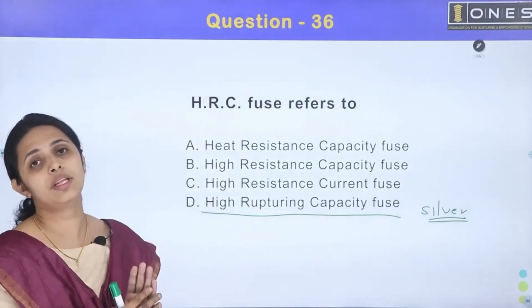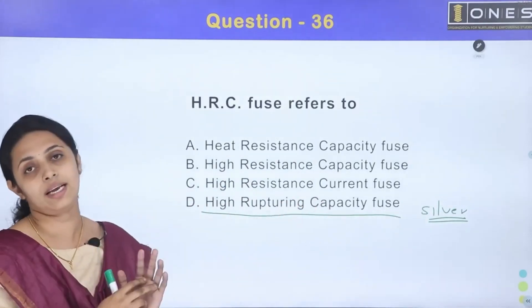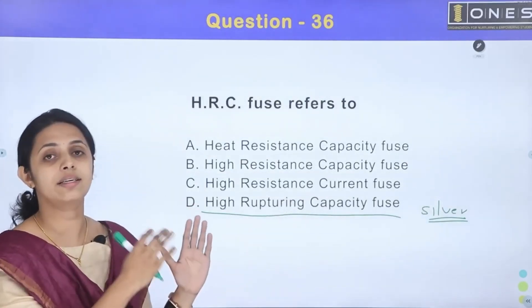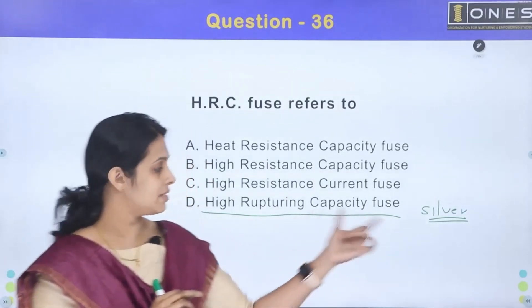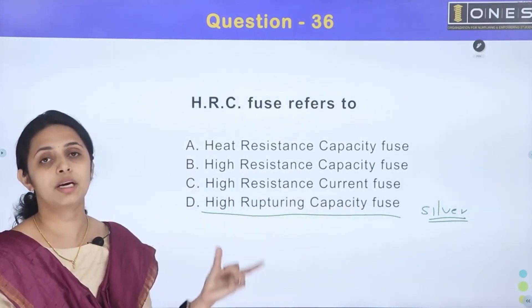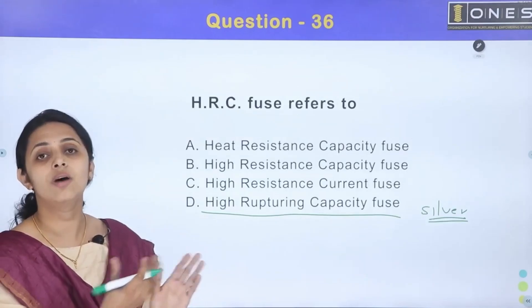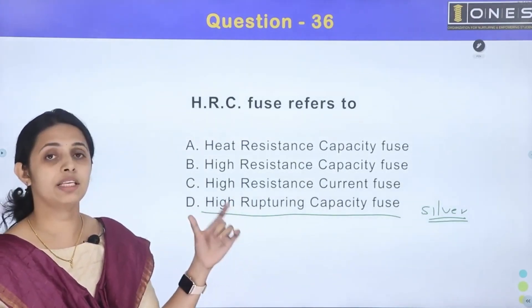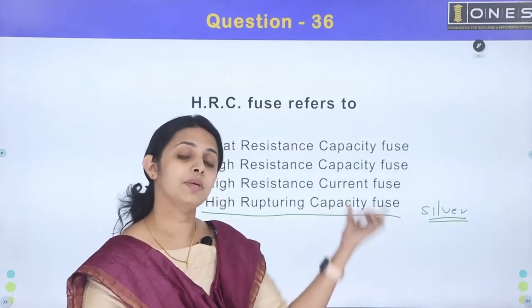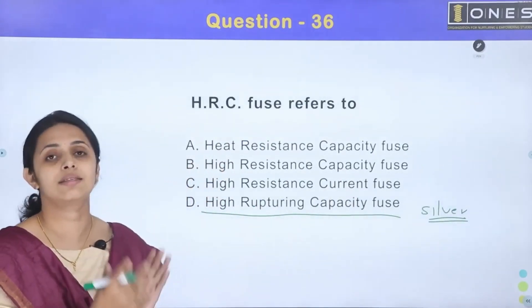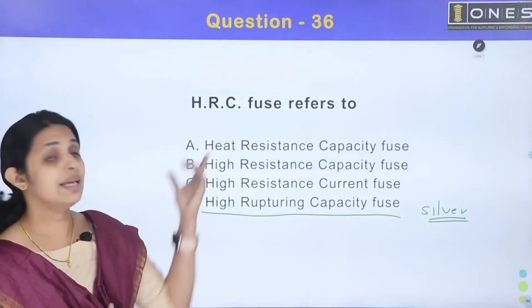The HRC Fuse uses a glass or quartz tube filled with powder. Inside, there are silver contacts, end plates, and a fuse wire. When high current passes, the silver vaporizes, and the quartz tube filling undergoes a chemical reaction to form a high-resistant substance, acting as a cooling mediator and interrupting the circuit.